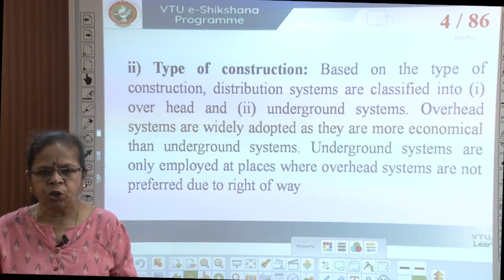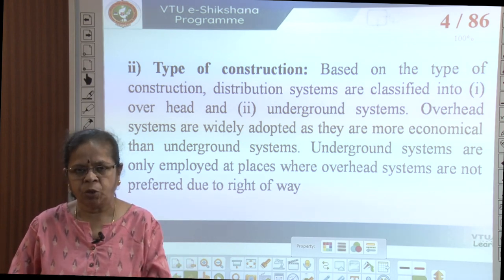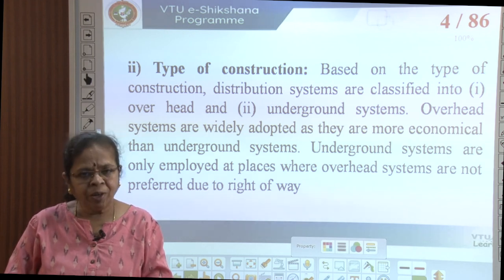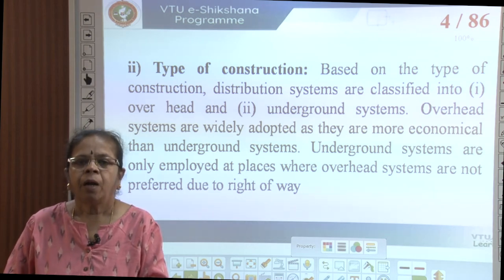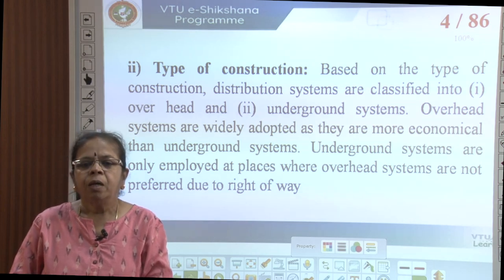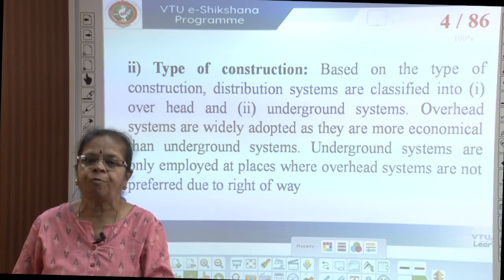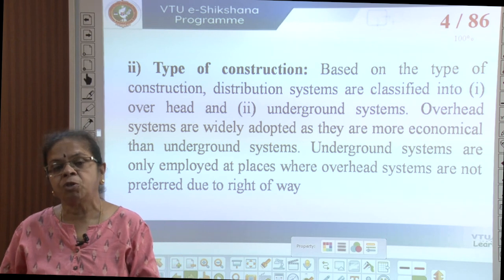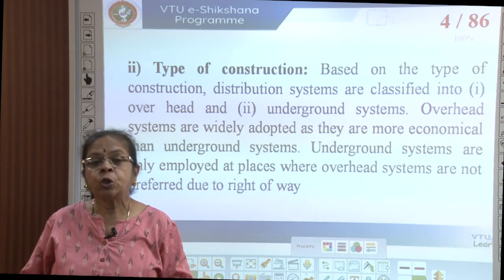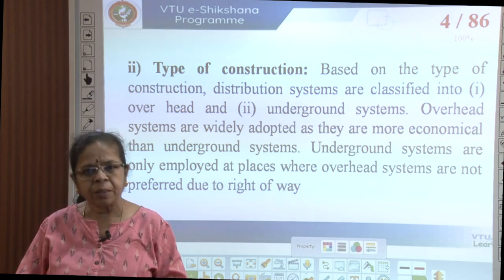Depending on the type of construction, just like in transmission, you have overhead distribution and underground distribution. In India, overhead distribution is most popular as it is cheaper. Underground distribution is used where aesthetics is important, where there is heavy transport, or water bodies. Underground systems are also employed where overhead systems are not preferred because of right-of-way. Right-of-way is an even bigger problem on the distribution side because you have residential and commercial establishments, making it expensive to acquire right-of-way for overhead lines.